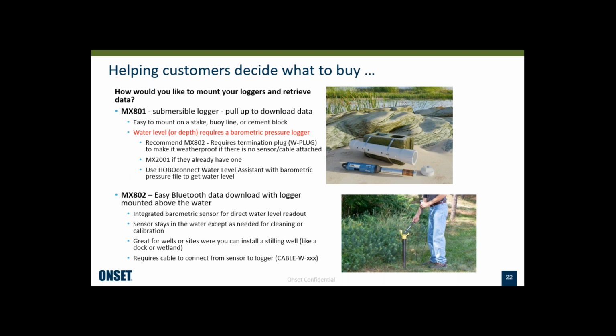On the other hand, if they've got a well, or they can put in a stilling well on a dock, for example, they may find that the MX802 is the easiest choice because that allows them to get barometric pressure directly. The logger includes the barometric pressure, and that provides water level directly. You can just walk up to the logger, connect to it, and you can see what the current water level is with the MX802. The sensor stays in the water while the logger head sits above the water. So it's got to be someplace where the user can make sure that it doesn't get flooded. But there's a lot of sites like on docks and stuff where they can do that. And it does require that they order a cable to connect from the sensor to the logger.